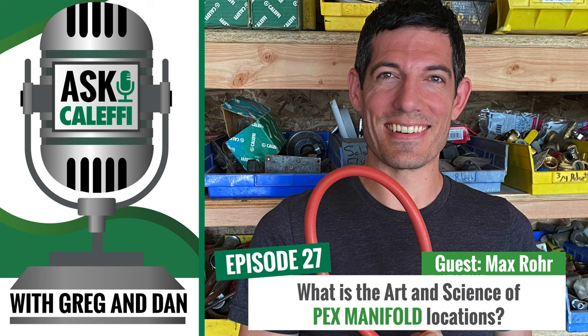Right. I think another good question that we get a lot is, hey, I have this manifold installed, everything pressure tested out fine, we're running the system through its paces, and I've got one zone that just is not heating. There's no flow through it. What do I have to do? Sounds like you need to do a little purging probably. You got it. Probably got some air bound up in that manifold or in that PEX circuit.